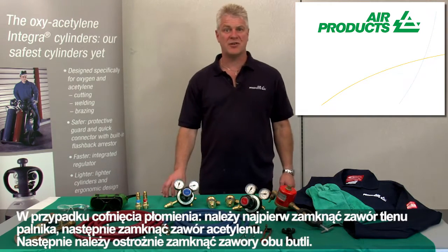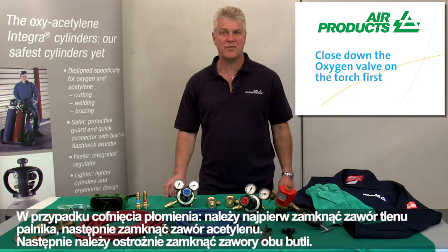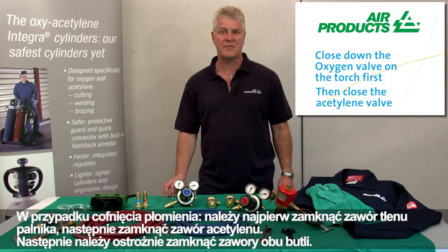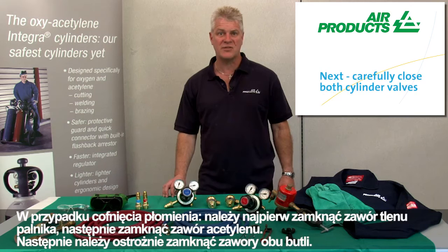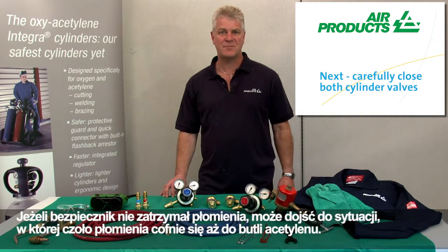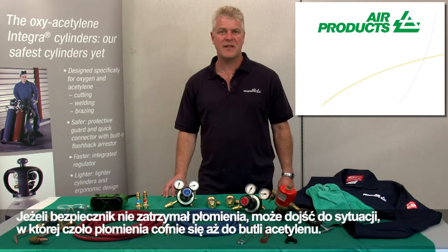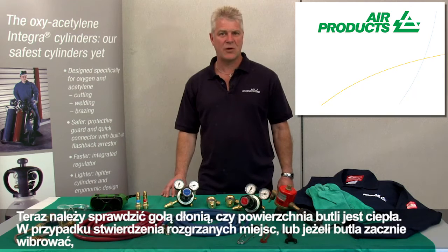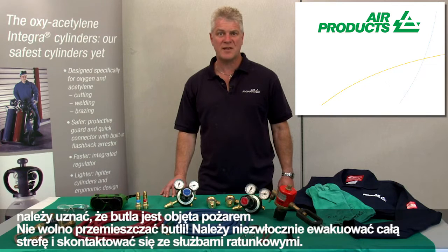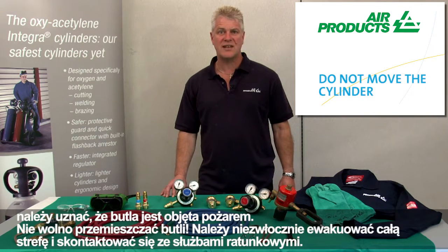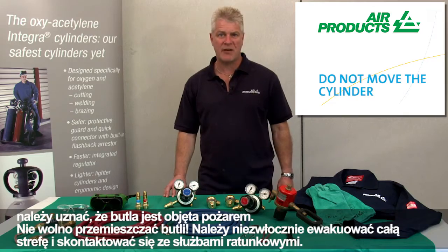If you get a flashback situation, close down the oxygen valve on the torch first, then close the acetylene valve. Next, carefully close both cylinder valves. If the flashback arrestor didn't stop the flashback, then the flame front may have entered the acetylene cylinder. Now check the cylinder for hot spots by running a bare hand over its surface. If a hot spot's detected or the cylinder begins to vibrate, treat it as if it's been involved in an external fire. Do not attempt to move the cylinder, evacuate the area immediately and call the emergency services.